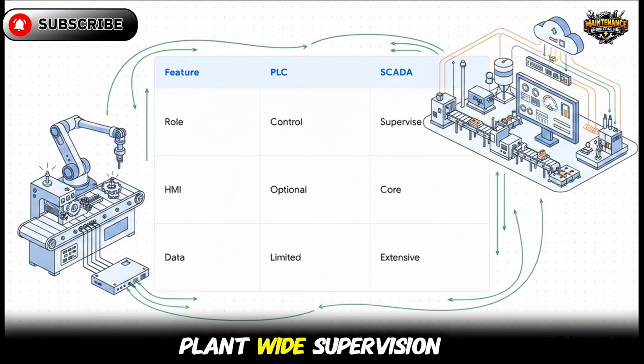Instead, it provides plant-wide supervision. It pulls in extensive data analytics, utilizes the HMI as a core feature for operators, and has advanced historical data and alarm management. Simply put, the PLC controls the machine, and SCADA monitors the entire plant. They are not competing, they're working together seamlessly.